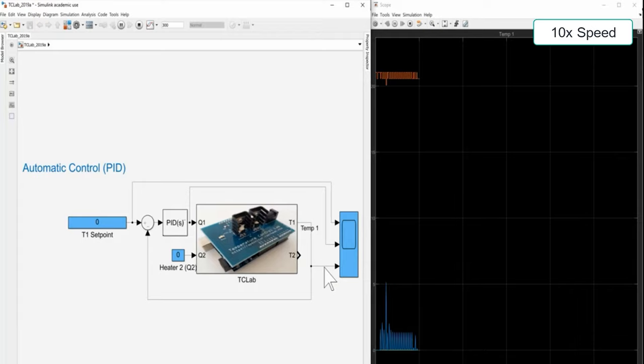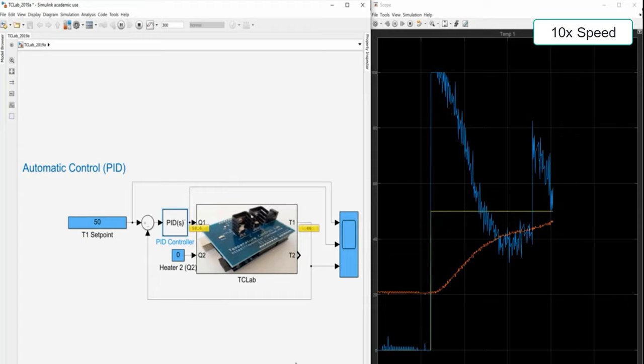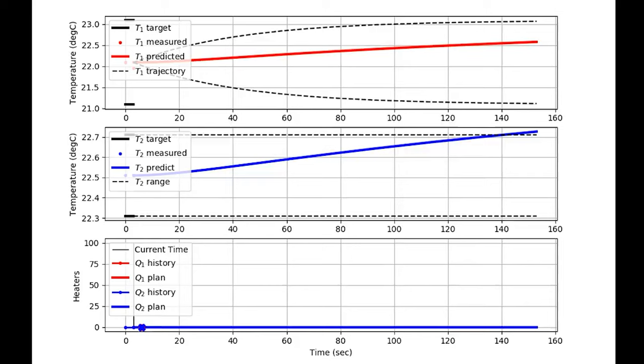Then they can see the response. As you change the set point, you can see the blue line which is the heater value, the yellow line which is the set point, and the orange line which is the PV value. On the fly, they can change the controller gain — for example, I changed it from 10 to 15 and you can see it made the response more aggressive. You can also see real things like measurement noise.